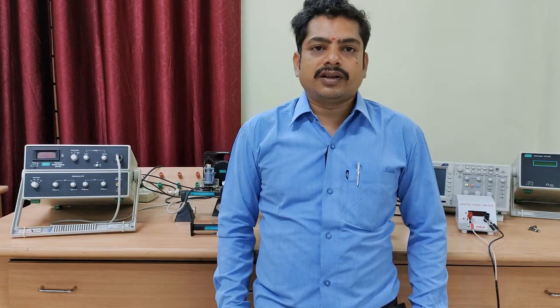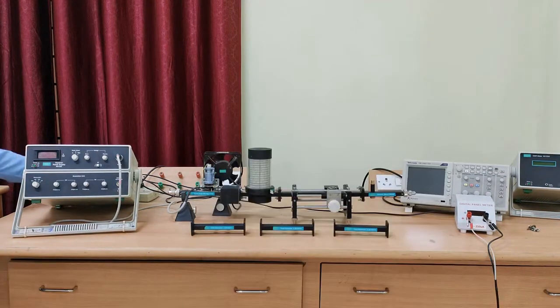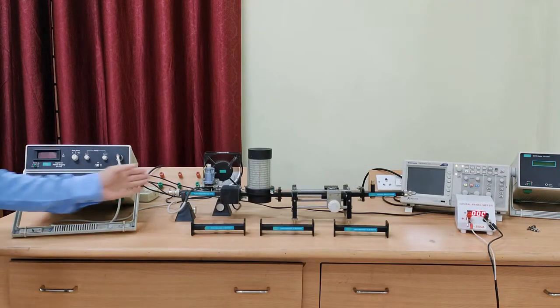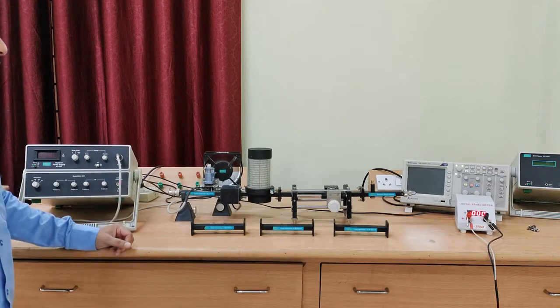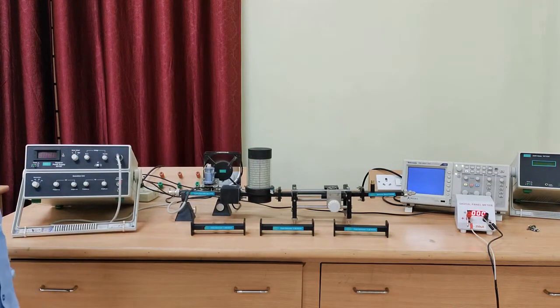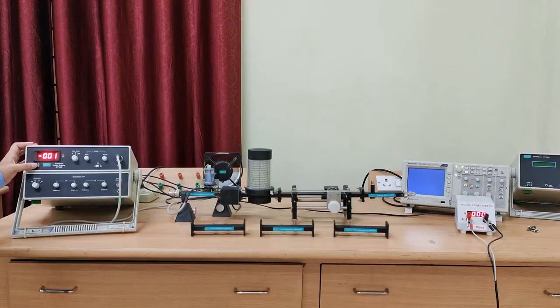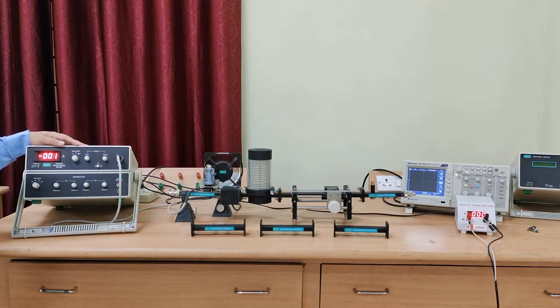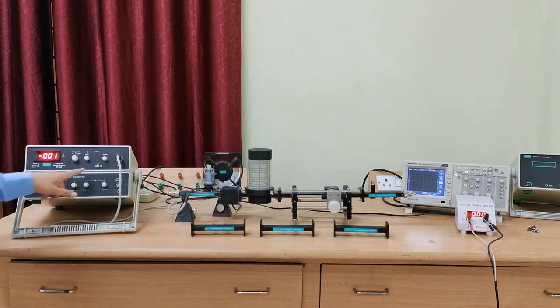Operational procedure of klystron power supply. Turn on klystron power supply and klystron fan, which are in devices. Pressing power button, klystron power supply is on. We can observe the readings of reference voltage, klystron voltage as well as current. Until we press HT mode, this should be in minimum voltage.